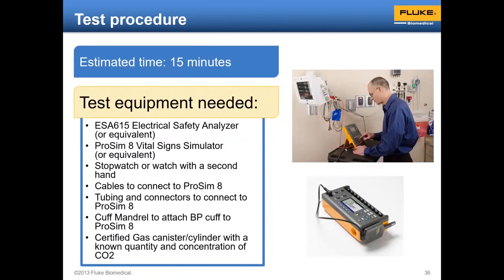All right, so how long should it take? Well, a 62353 direct method should not take more than 15 minutes to do the whole test. And in fact, it shouldn't take more than about 5 minutes to do the full electrical safety test on a patient monitor. What kind of test equipment would we expect to need for the full patient monitor test?